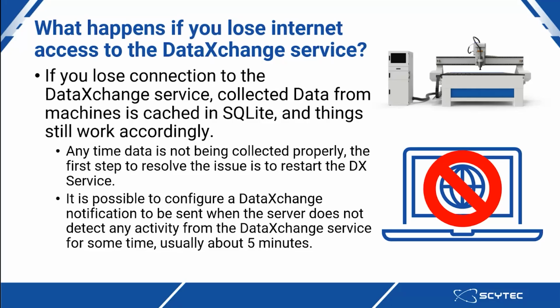And anytime that data is not being collected properly, the first step to resolve the issue is to restart the DataXchange service. And it is possible to configure a DataXchange notification to be sent when the server does not detect any activity from the DataXchange service for some time, usually about 5 minutes. So you can get a notification in either Microsoft Teams, text, or email alerting you that the DataXchange service has stopped communication and that you can go out and restart it.